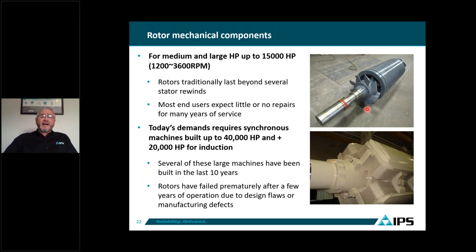With the high demand for synchronous motor horsepower, it's not unusual to see 30,000, 40,000, even 50,000 to 60,000 horsepower synchronous motors. These machines have far more components than induction motors — field coils around the salient poles, connections, blocks, bolts, the rotor exciter, and the rectifier wheel. However, we don't see the rate of failures that we see with induction motors.